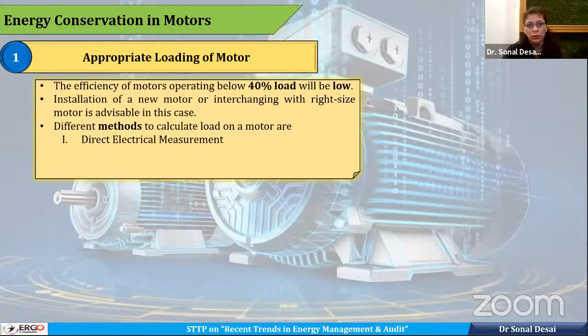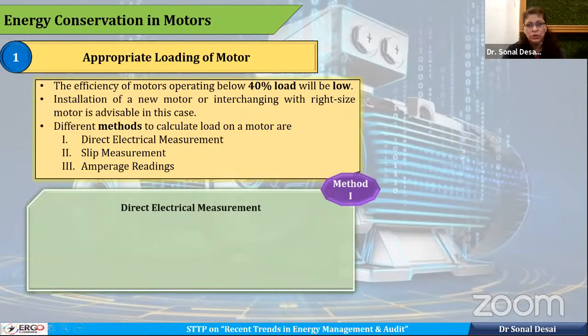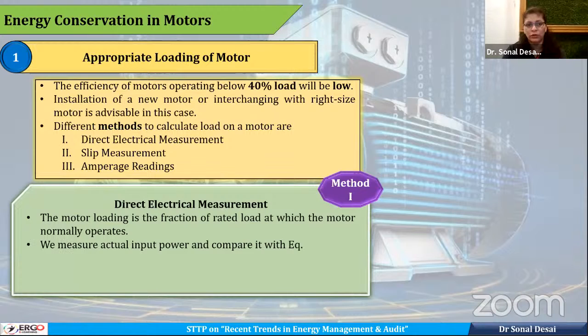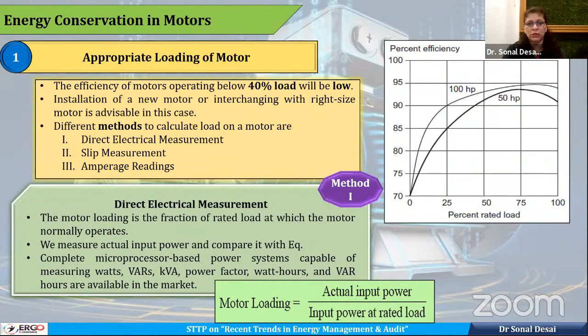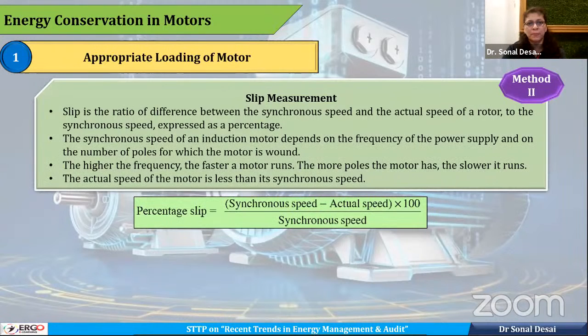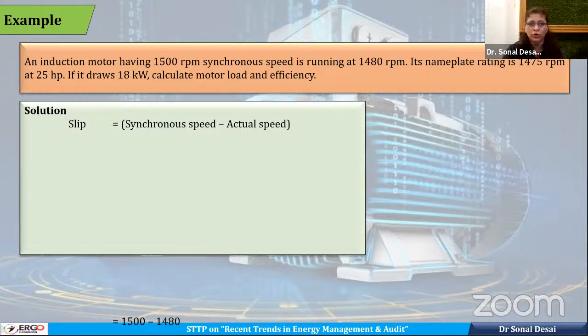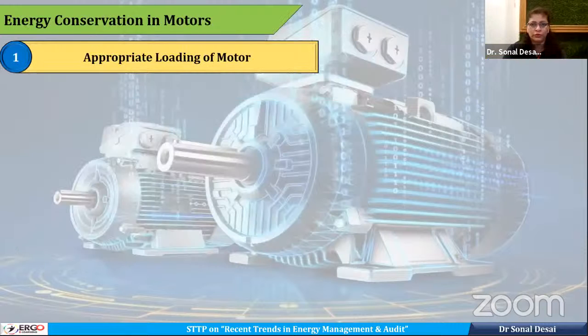So how to check motor loading? From electrical fundamentals, there are three methods to identify loading of the motor. One method is direct electrical measurement. Another method is slip measurement, that is change in speed. And third is nameplate or amperage reading, which can also confirm the loading of the motor. I'm not going into the details of how to confirm loading of the motor. By these three methods, loading of the motor can be calculated. And by knowing this loading, we can identify whether the motor is perfectly loaded or not. For all these three methods to calculate loading, examples are given. So those who want to refer to that can refer to these PPTs later.